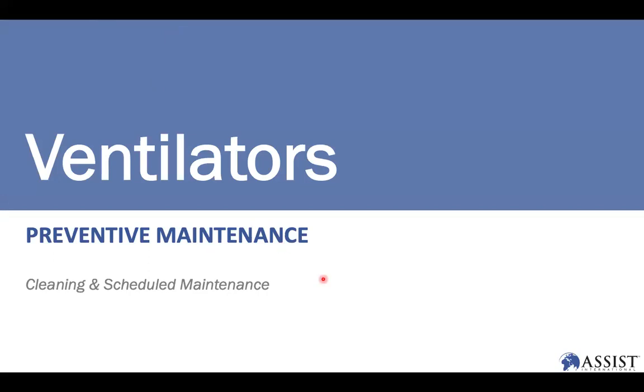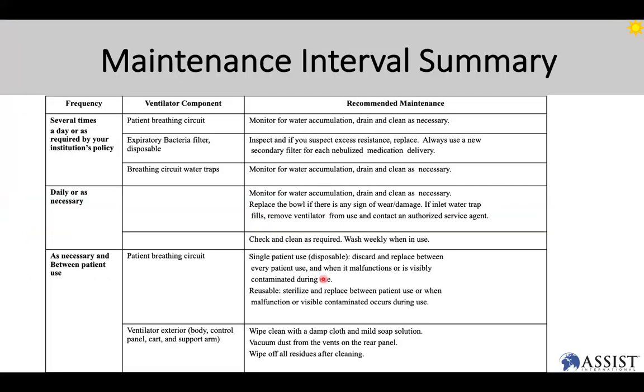So we will begin with some cleaning procedures for a ventilator. For a patient breathing circuit, it is recommended that you clean the circuit multiple times in a day. You want to monitor for water accumulation, drain and clean as necessary. Please note, if you have a patient that is COVID-19 positive, coronavirus positive, be very careful as you handle liquids. You want to dispose of the HEPA filter. The recommendation is that you do that every 4 hours if you have enough supply. If not, you definitely have to replace that filter between each patient.